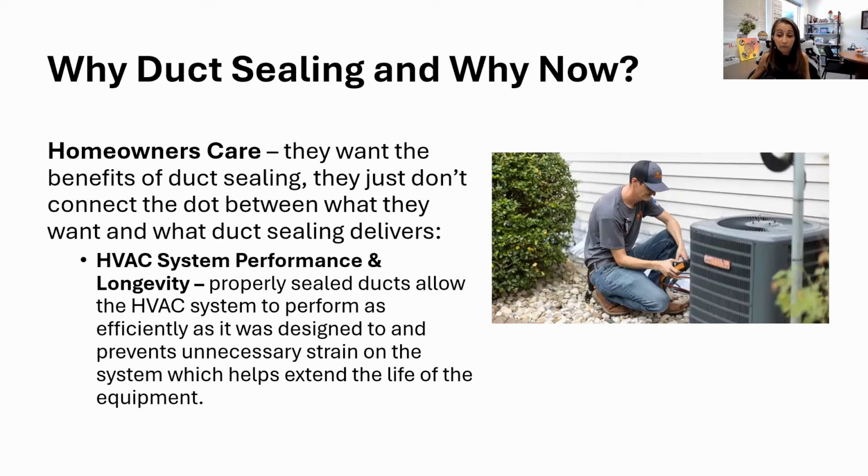Yeah. Jared, one of the things we've seen related to that, when a home switches over to a heat pump, or even in cooling for that matter, and it's struggling because of duct leakage and we're not getting the CFMs to the distant registers or rooms, a common answer is to turn up fan speeds. So they'll turn up fan speeds to get more CFMs to those rooms, and they will get more CFMs, but the temperature rise will decrease in heating mode, and that exacerbates some of those problems you discussed. So sealing that ductwork to make sure you're getting 100% of the air that leaves that furnace or air handler to your rooms is really important when you switch over, for comfort.